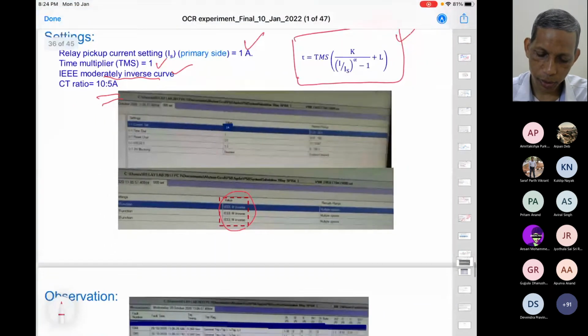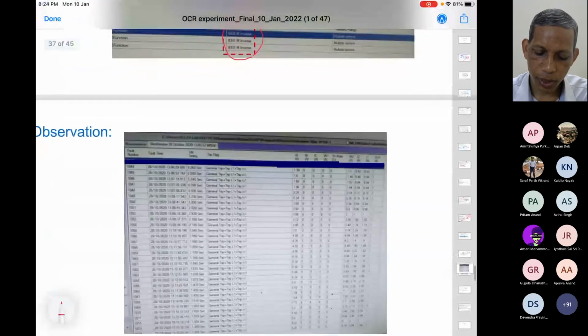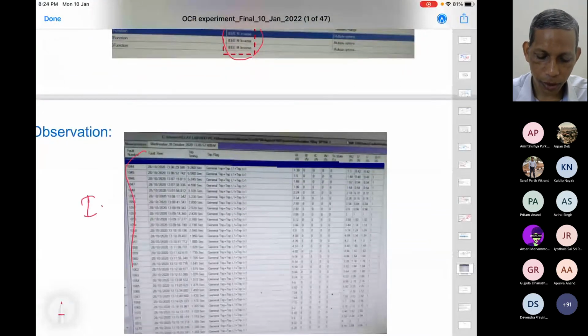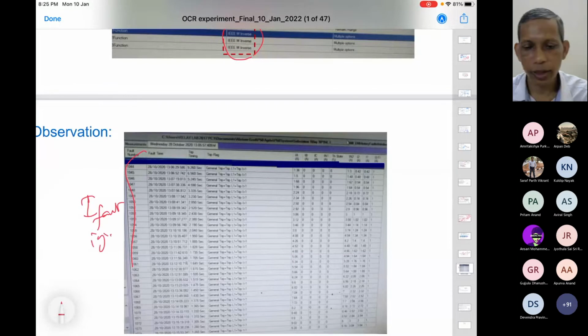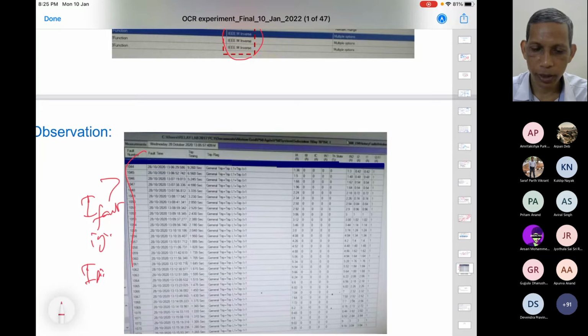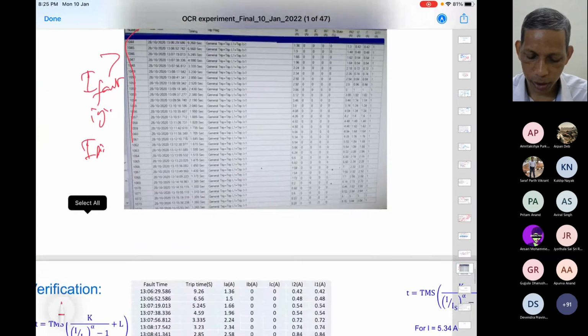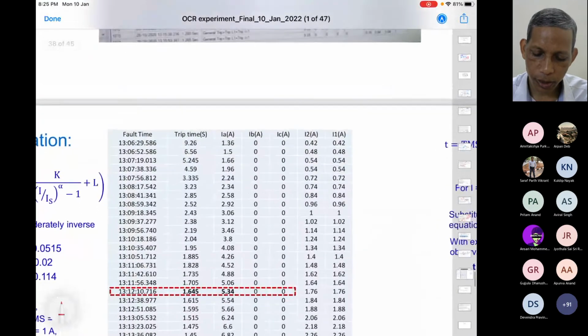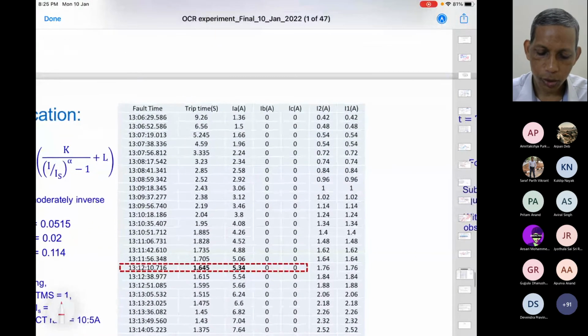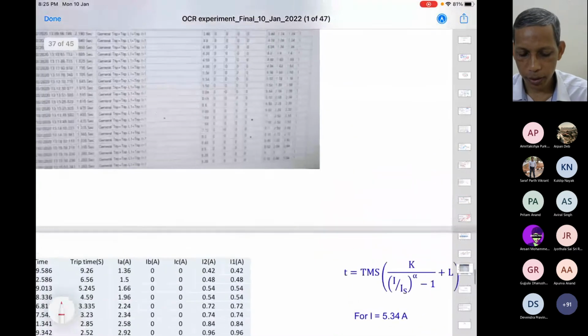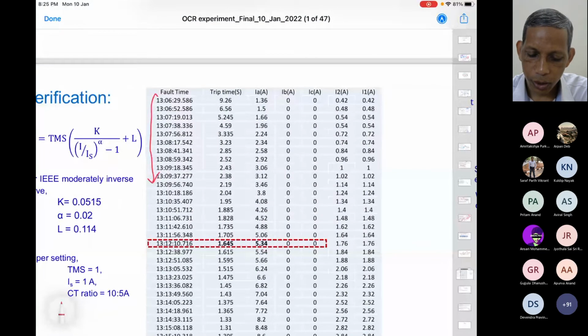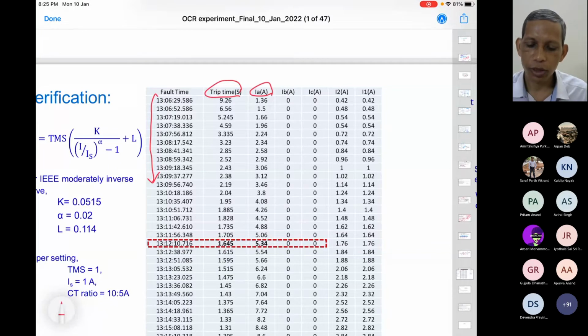These are the things available in the relay, and we can have a glimpse of what the relay provides. Then we took the observations for different fault current injections, greater than the pickup current, which is 1 ampere for this system side. We noted these in tabular form, with the trip time. We created a phase A to ground fault, and the other phase currents we made 0. So this is a phase A to ground fault and this is a ground relay, not phase relay operation, ground relay operation.